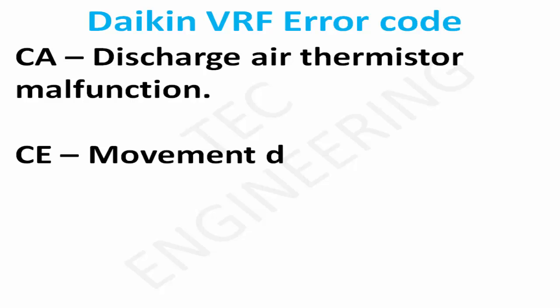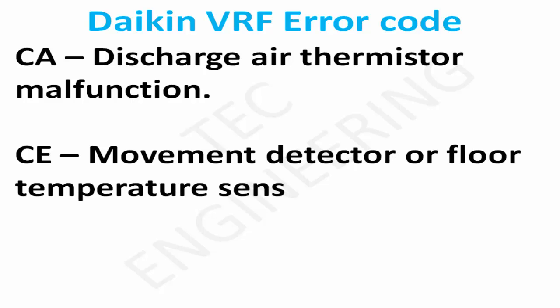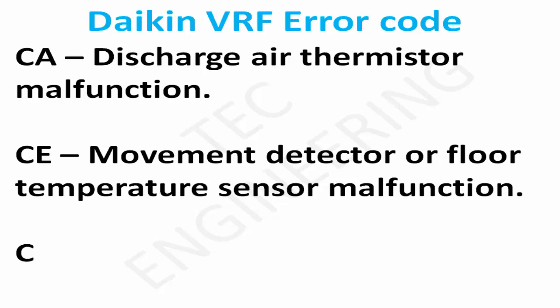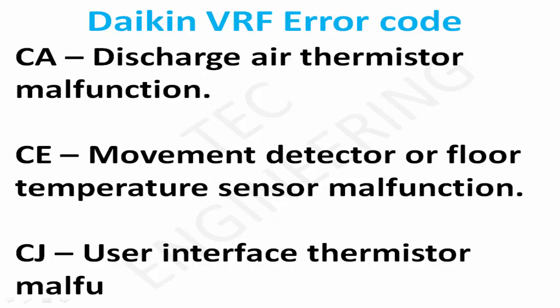CE: Movement detector or floor temperature sensor malfunction, indoor. CJ: User interface thermistor malfunction, indoor.